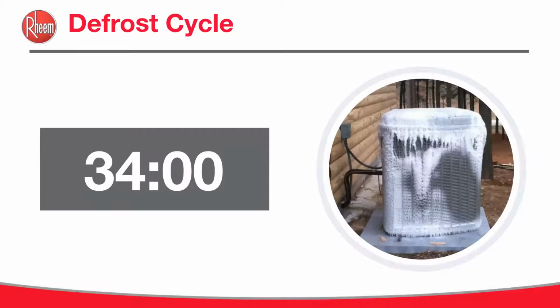Let's look at defrost. Defrost is a cycle which is required for heat pumps. Yes, this may not be what units look like. First thing you see here is when you look at it, you go, wow, who installed that, right? Because it's not installed above grade. And that's one thing that you have to look at when you're installing a heat pump versus an AC. You have to make sure it's raised off the ground for proper water drainage in defrost mode.